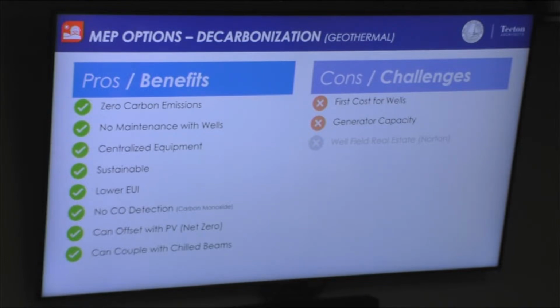Any sense of what the cost for those wells would be? It could vary, we've been seeing the cost anywhere between $20,000 and $30,000 per well. And what that means is that's a total cost, that means the well system, the well field, piping brought into the building. That's where we've been seeing it on the last 10, 12 jobs in that range. And how many wells would we need for the school? For this one, we're at 101, 102, in that range, and that's where we are right now. When we start out a project, we size the well field based on a rule of thumb, what we've seen. And if we're going to go forward with a geothermal system, we recommend you get a test well done. The test well will tell us the thermal conductivity of the ground, how deep the bedrock is, so we know the casing, so we control the cost, and we can then right-size the well field. Typically our well field sizing goes down after schematic once that test is done, because once we put it into a geothermal program, based on our model it'll tell us exactly what we need, the longevity of it, what our temperature rise is going to be, and we can right-size the well field instead of just using a rule of thumb.